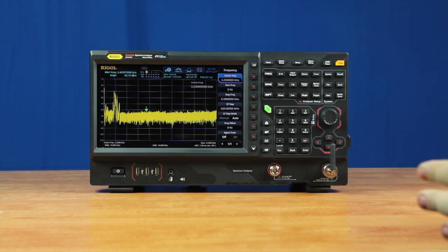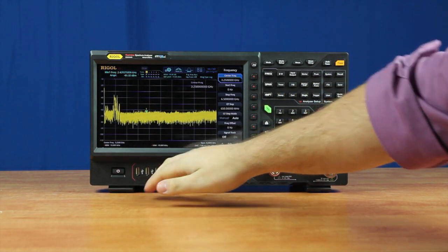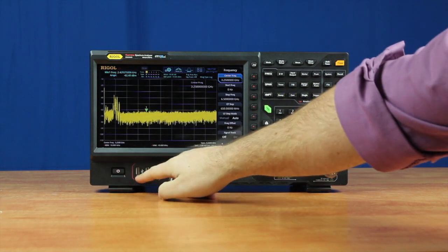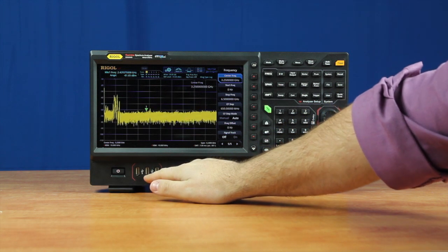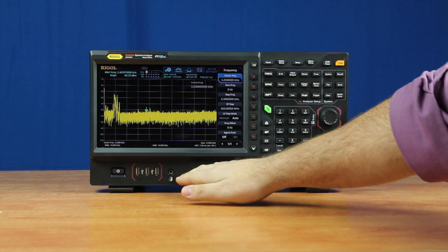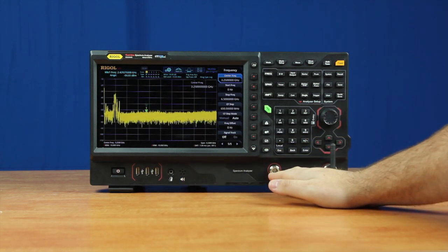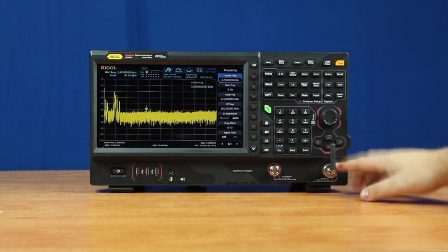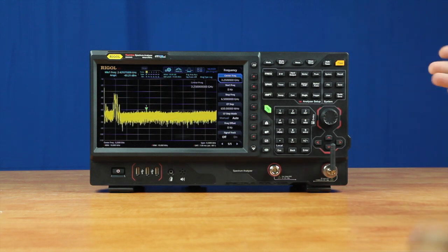On the front panel of the RSA5000, we've got our power button, three USB ports — one for your USB stick or flash drive, your wired keyboard and mouse if you so desire, and audio out for headphones or speaker. We have our tracking generator, which is available on all TG models. And then we've got our input, which currently has a 2.4 GHz antenna so we can see the Wi-Fi going on in the room.